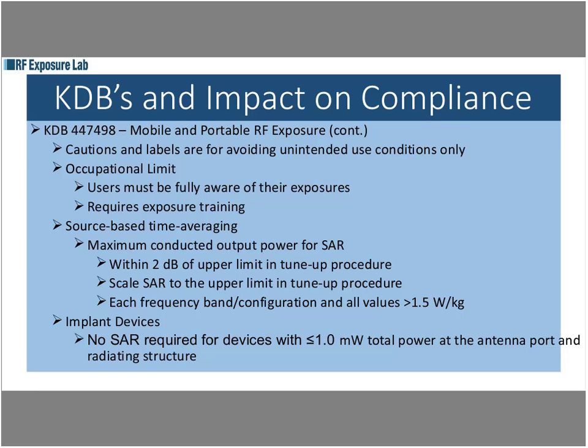You do the measurements at the maximum conducted power for SAR, and in SAR, this is where I fight a lot of times trying to get clients to understand, I need a tune-up procedure on their transmitter. I need to understand what their upper limit is, and the transmitter, when I'm doing the testing, must be within 2 dB of that upper limit.